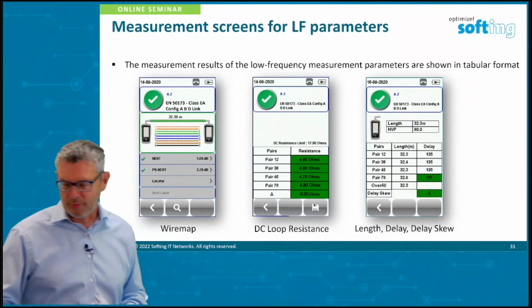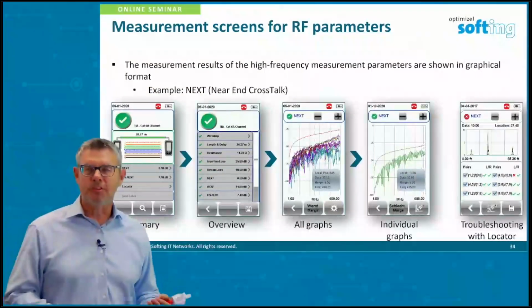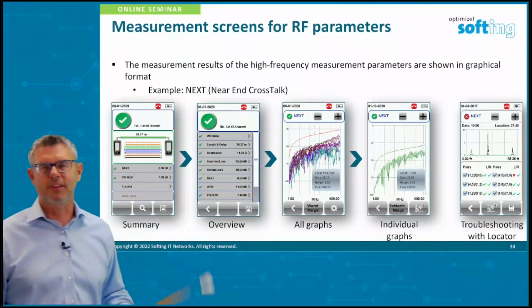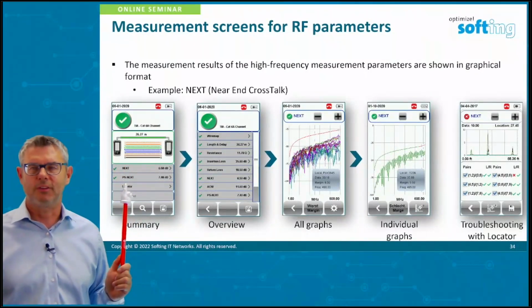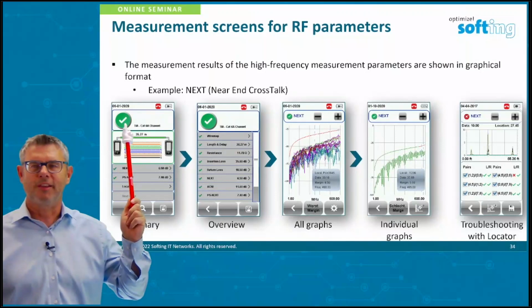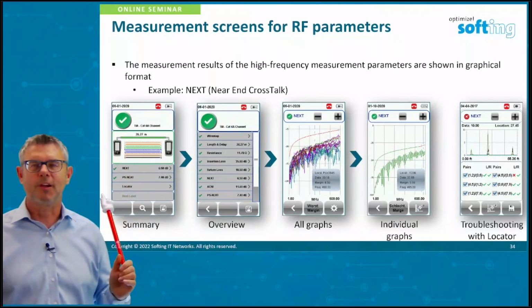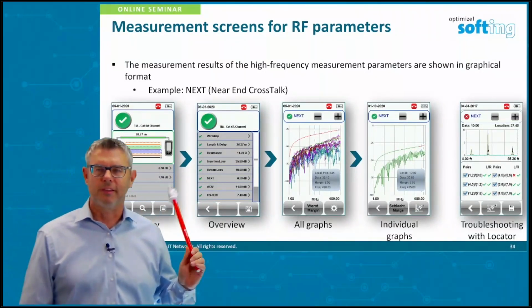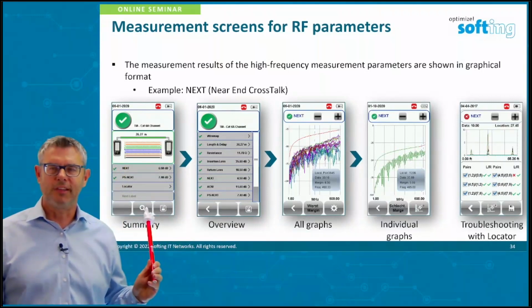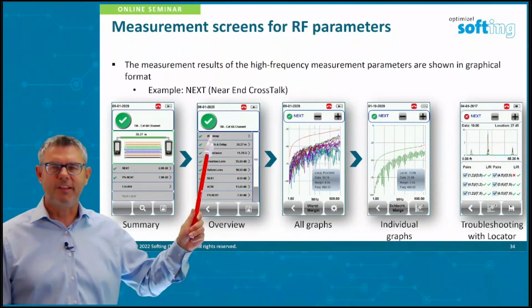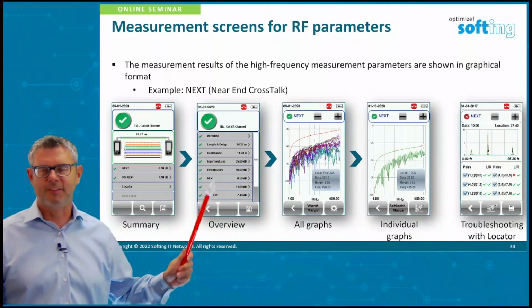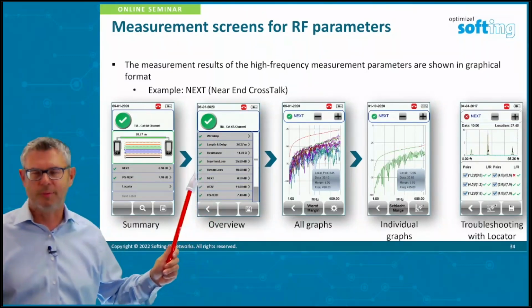Okay, when the instrument is doing an RF measurement, a high frequency measurement, you get even more screens out of the tester. It starts again with a summary screen when the test is finished. Lovely, we were happy and got a very nice green tick mark here. Then we can dig down into the details, and we see a complete listing of all the parameters which were tested. As I said, 14 to 15 parameters nowadays.